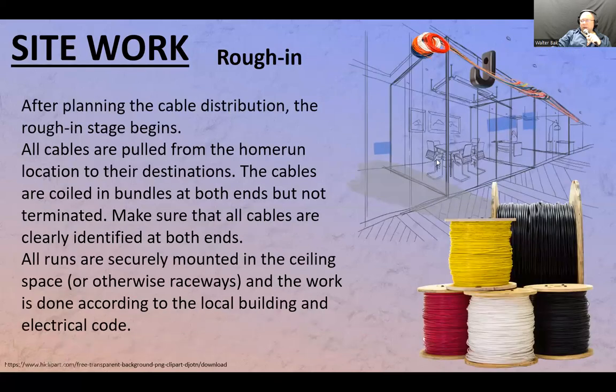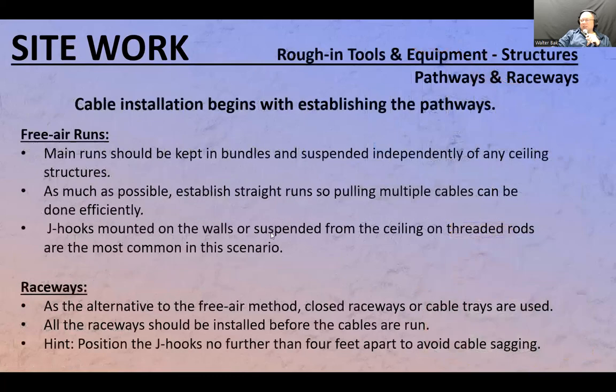Again, let's go back to this point. Establish the J-hooks no further than 4 feet apart. If you have them separated further apart, then the sagging begins. The problem with sagging is, well, first of all, it's aesthetics, but who cares about aesthetics after the ceiling is covered, nobody sees that anyway, right? But the real problem is that at the point of contact, there's too much pressure when the cables are sagging, and that's just like the cable being stepped on or deformed otherwise. That means it can change the specifications of the cable, so Cat 6 or Cat 6A might not be Cat 6A anymore.